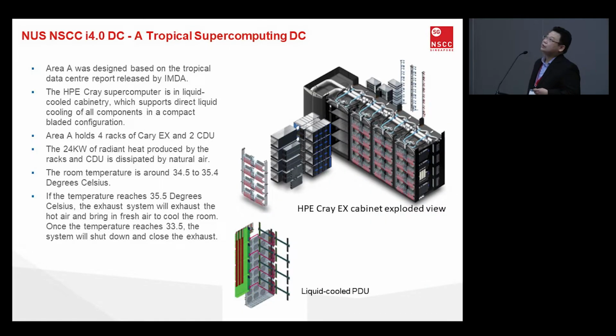All right, so as mentioned, area A is designed using the IMDA Tropical Data Center report. So how this works is that we look at the equipment that we're going to put in, based on the ASHRAE psychrometric chart of the system. We can figure out how high a temperature the system can take before it goes into failure. So what we do is that we find a sweet spot and we push the limit, we push the system as much as we can so that we do not expend additional resources or cooling energy on the system itself.